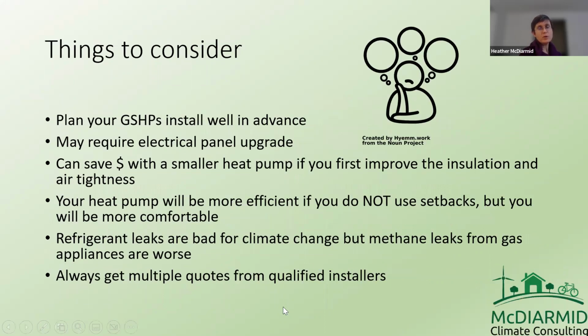There are a few other things to consider if you're thinking about a ground source heat pump. You want to plan that installation well in advance, since the infrastructure you need to invest in is a bit more complicated. You may require an electrical panel upgrade, moving from 60 or 100 amps to 200 amps service. While planning for that installation, it can be worthwhile to get a home energy audit and find out what it would be cost effective to do to improve the building envelope, because you can save money with a smaller heat pump if you reduce the heating load.